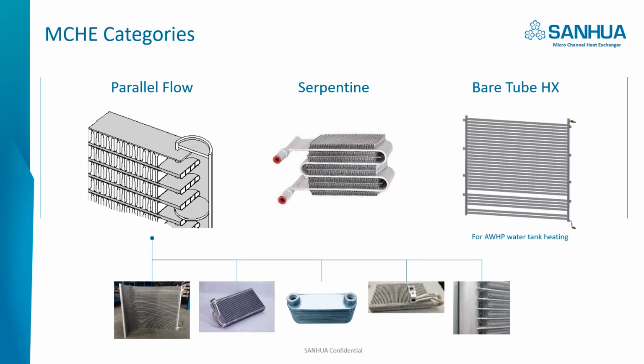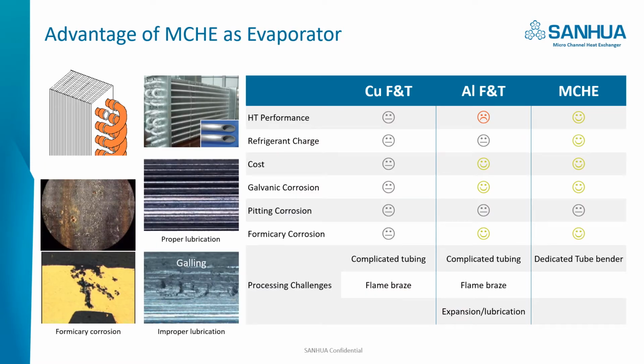Still, the majority is a parallel flow, and it extends from standard condenser to the parallel flow evaporator, the oil cooler, parallel flow evaporator, and also the new style of heat pump microchannel. Microchannel heat exchanger is very familiar to the industry as a condenser due to its higher heat transfer performance, less refrigerant charge, less cost, better galvanic corrosion, comparable pitting corrosion. And as an evaporator, the copper fin and tube heat exchanger has a formicary corrosion issue, but microchannel heat exchanger is all aluminum, so no worry about that.